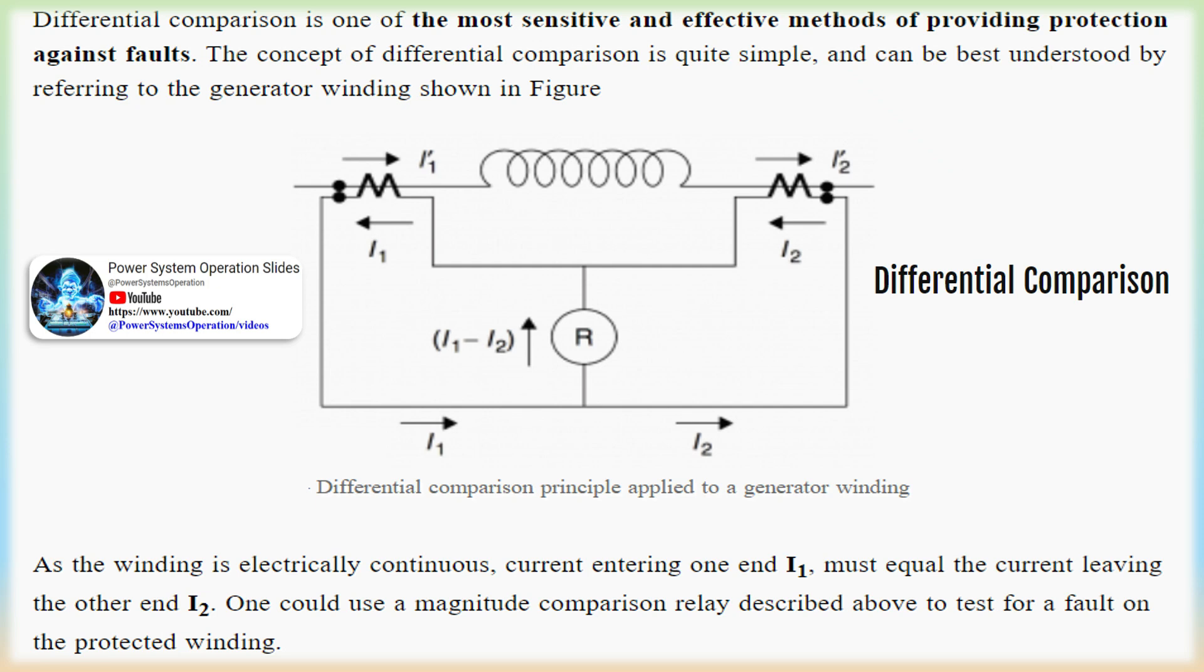Differential comparison. Differential comparison is one of the most sensitive and effective methods of providing protection against faults. The concept of differential comparison is quite simple, and can be best understood by referring to the generator winding shown in figure. As the winding is electrically continuous, current entering one end, I1, must equal the current leaving the other end, I2.